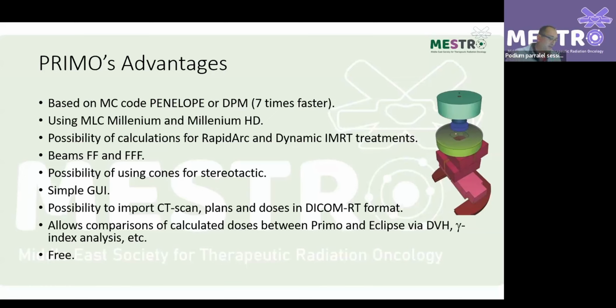There's a possibility of using cones for stereotactic treatments. The graphical user interface is very simple and easy to use. There's a possibility to import CT scans and plans via DICOM-RT. And PRIMO allows comparison of the calculated dose between PRIMO and Eclipse via DVH and gamma index analysis, plus it's free.